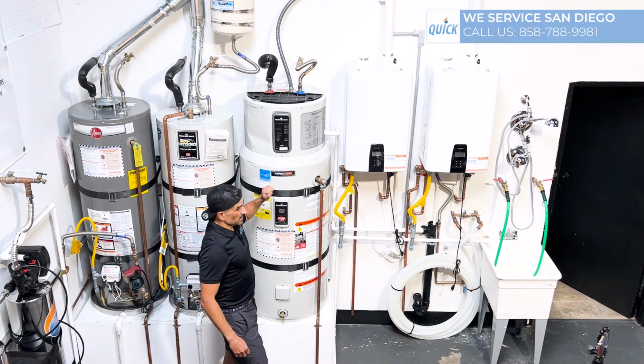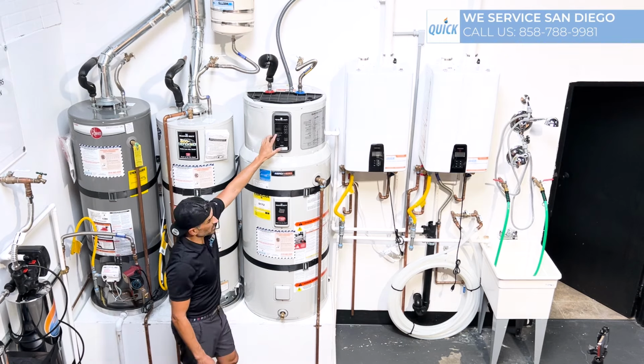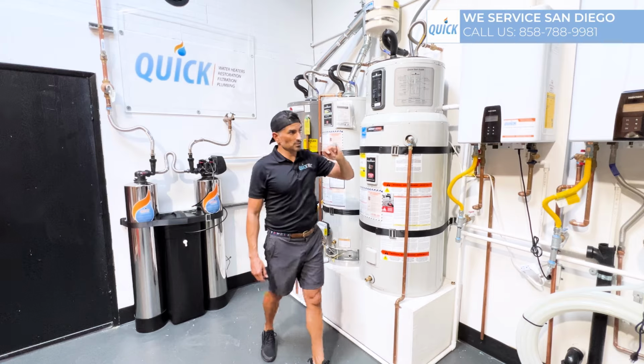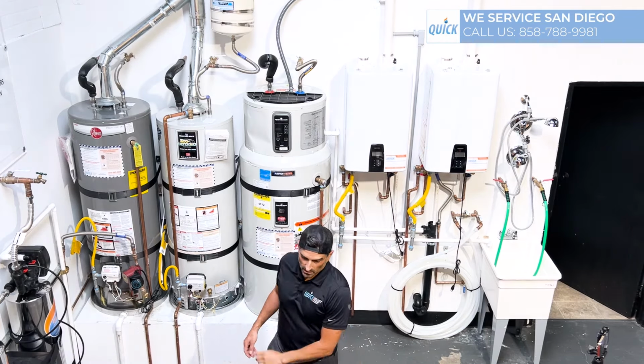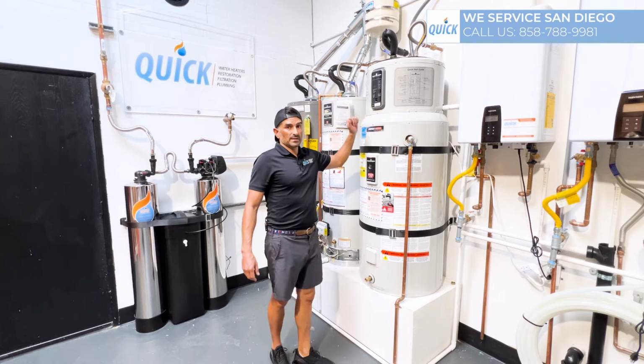This water heater in condenser mode, which is why you're buying the water heater to begin with, heat pump only, produces about 6 gallons an hour. In contrast, one of the larger tankless water heaters produces about 220 gallons an hour. So if you take a bath, you're basically toast.